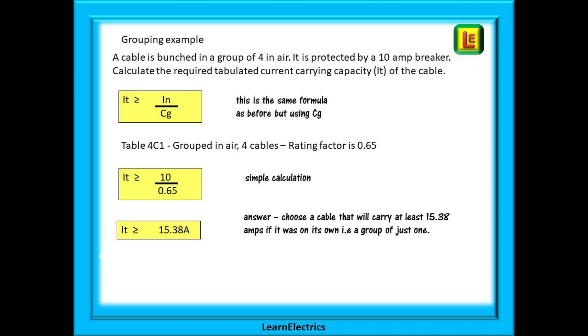A cable is bunched in a group of 4 in air. It is protected by a 10 amp breaker and you must calculate the required tabulated current carrying capacity IT of the cable. This is the same formula as before except now it is for groups of cables instead of air temperature. Pause the video and work through this example. This is an easy calculation and your answer should be 15.38 amps.